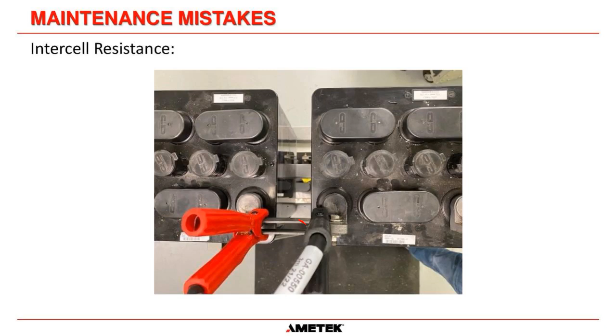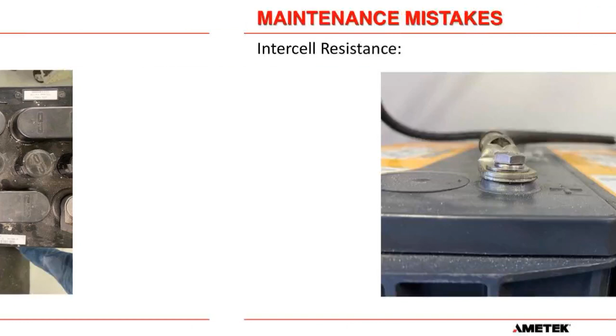So it drives me insane when I see people taking measurements and they put their clamps on like this. They do it all the time, all the time. If you put a clamp and it touches this bus bar in any way, shape, or form, the reading you're getting is of no significance whatsoever. Hopefully that explained that.